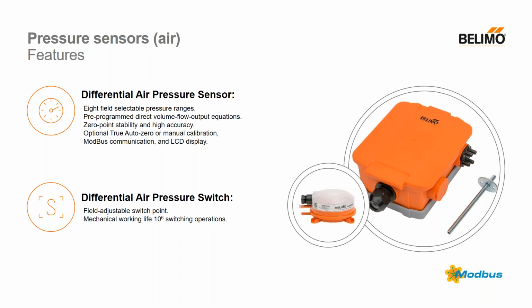They're available with a manual or a true auto calibration. So if you've got DP sensors that are either located in spaces that are difficult to get to or in critical applications, that true auto zero calibration can prevent you from having to go back and either get into a tight spot or infringe on the day-to-day operations of maybe an operating room or some sort of critical environment. Again, this particular product offering, the airside DP, presently is only available with Modbus. We do not have BACnet at the time. I'm not sure if BACnet's coming on the airside DP, but I will keep everyone posted and let you know what happens there.